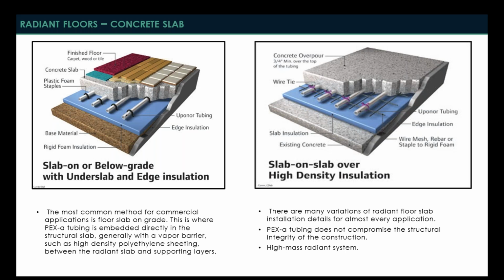So one point to make is that the PEX-A tubing does not compromise the structural integrity of the construction. There are a lot of different ways that you can apply this. There are probably dozens and dozens of slab details showing how these can be applied. It can be put directly into a structural slab. It can be put directly into an overpour or a topping slab. So there's several different ways that it can be done. And the other thing to note about radiant floor slabs is this is considered to be a high mass radiant system. And a little further on into the presentation, we'll talk about the difference between high mass and low mass radiant systems and the pros and cons of each.